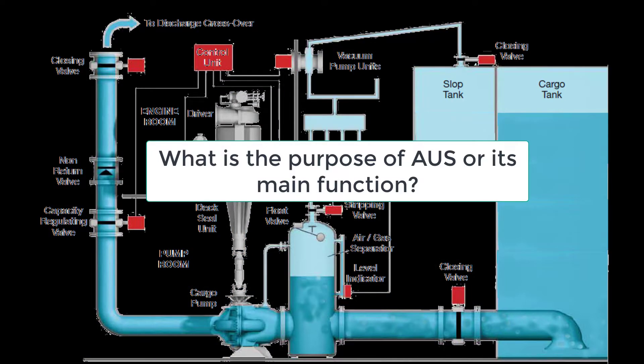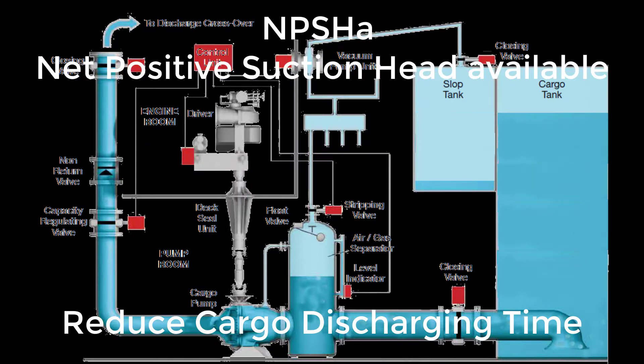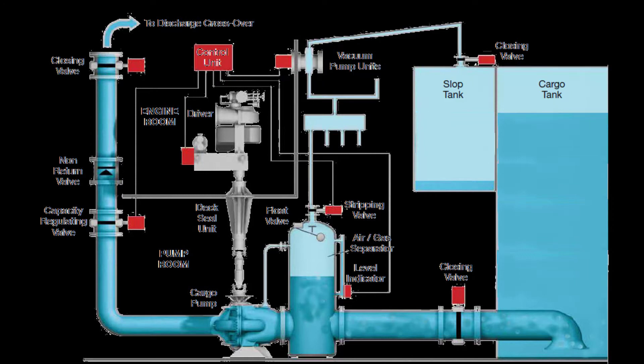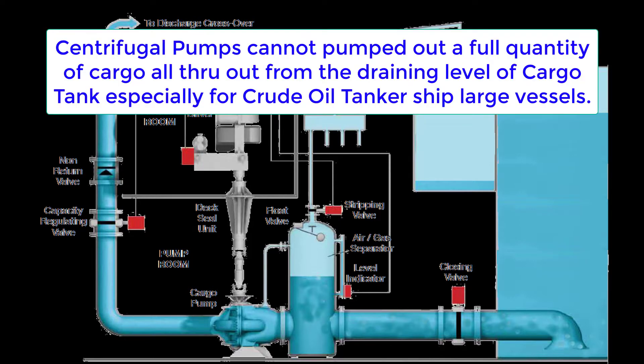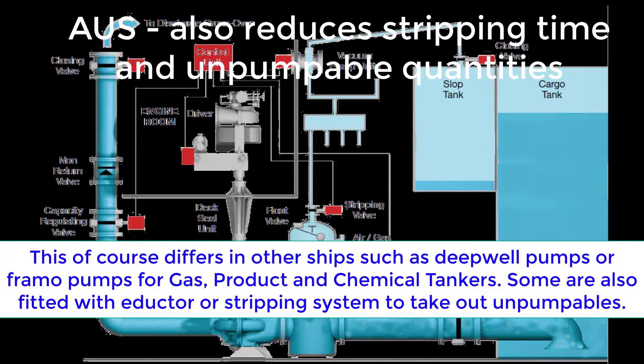What is the purpose of AUS or automatic unloading system? The purpose is to reduce cargo discharge time and to protect the pumps. When we talk about net positive suction head — when the available NPSH becomes low, wherein the suction side pressure is lower than the vapor pressure within the cargo tanks — it creates bubbles. A centrifugal type pump cannot actually discharge the full cargo volume of a tank; eventually it loses suction and cavitation takes place, leaving some unpumpable quantities. Thus, the AUS optimizes the cargo pumps to their maximum performance before stripping of cargo tanks takes place, reducing stripping time and unpumpable quantities.